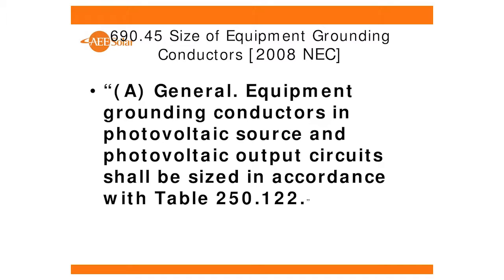Size of equipment grounding conductor: basically, the easy way to think about it is that we're allowed to use Table 250.122 for the size of our equipment grounding conductor, which is based on the size of the largest overcurrent device, and then it goes into a lot of detail about what if you don't have an overcurrent device and what you would use for that. But suffice it to say that when you're worried about the equipment grounding conductor size, the easy answer is on small circuits, 30 amps or less. If you're using 10 gauge conductors for your current carrying conductors, you're always going to have the same size equipment grounding conductor, even though, if you do the calculation, you could live with a smaller size. Smallest size allowed is 14 gauge.